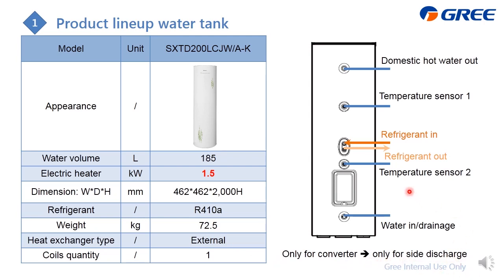And for this one, the refrigerant goes in and comes out, and there are two temperature sensors. One is for display for the user, and the other one is for the system to control the water temperature. And here is the water inlet, and also the water discharge. And here is the domestic hot water outlet. Inside there is only one coil.